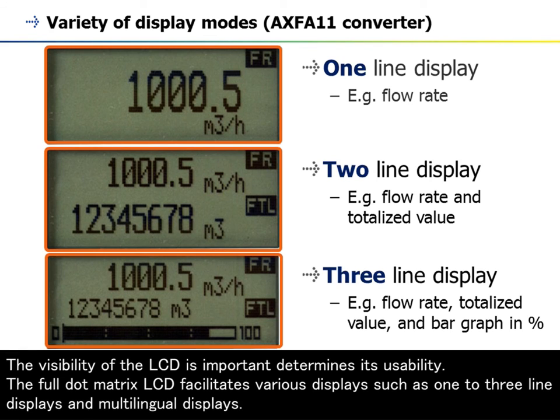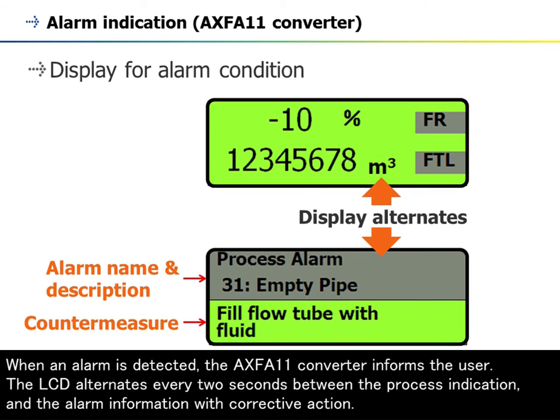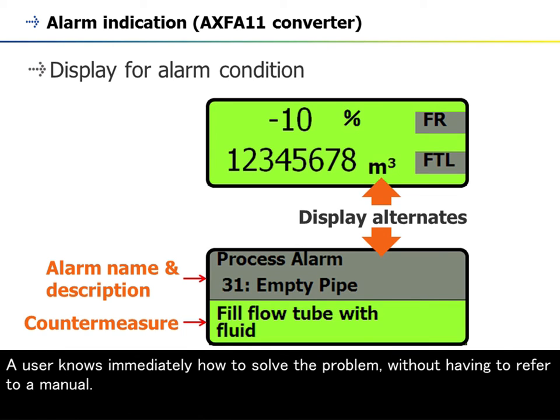The visibility of the LCD is important as it determines usability. The full dot matrix LCD facilitates various displays such as one-to-three line displays and multilingual displays. The LCD can display flow rate and quantity at the same time, and the percentage can also be displayed as a bar graph. When an alarm is detected, the AXFA11 converter informs the user. The LCD alternates every two seconds between the process indication and the alarm information with corrective action, so a user knows immediately how to solve the problem without referring to a manual.